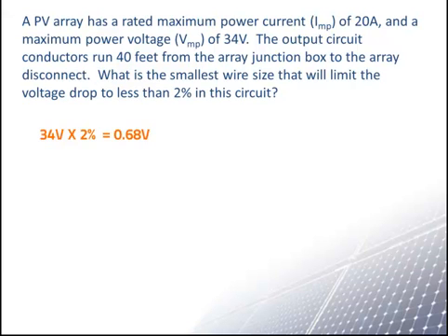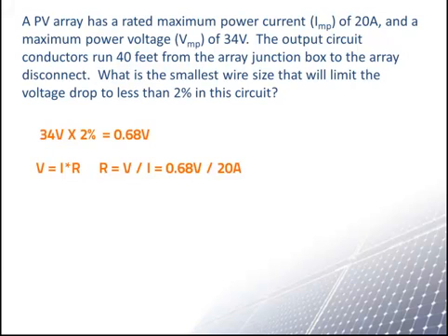Next, we determine the maximum conductor resistance allowed for the PV output circuit using the allowable drop and the given current. We can use Ohm's Law and rearrange to solve for resistance using the allowable voltage drop and current. Plugging the numbers in: 0.68 volts divided by 20 amps gives a resistance of 0.034 ohms.